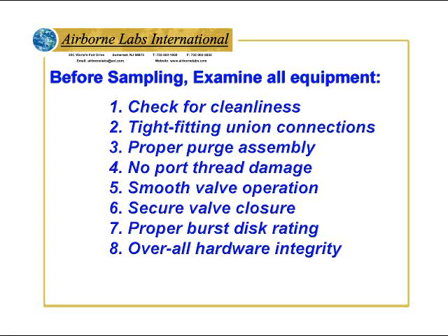Before sampling, examine all equipment. Check for cleanliness, tight-fitting union connections, proper purge assembly, no port thread damage, smooth valve operation, secure valve closure, proper burst disk rating, and overall hardware integrity.